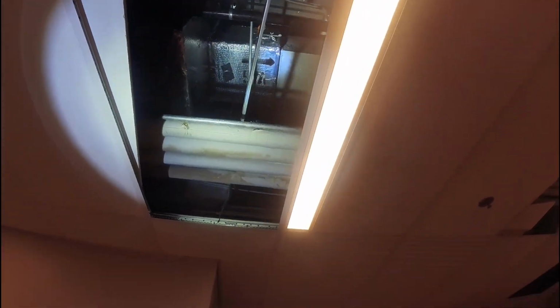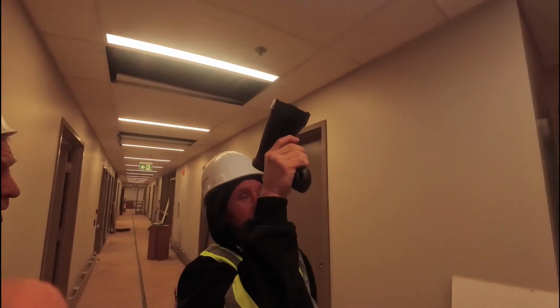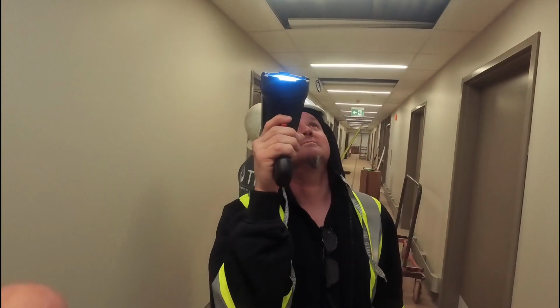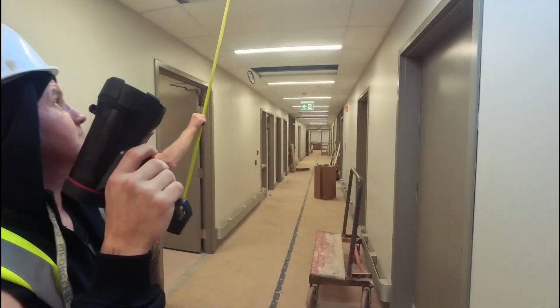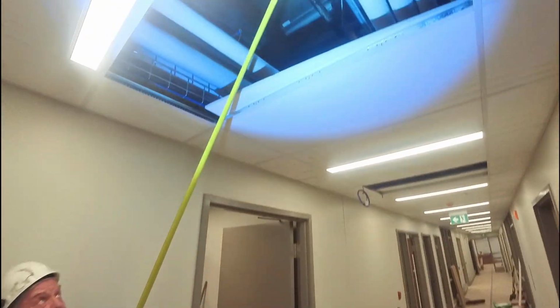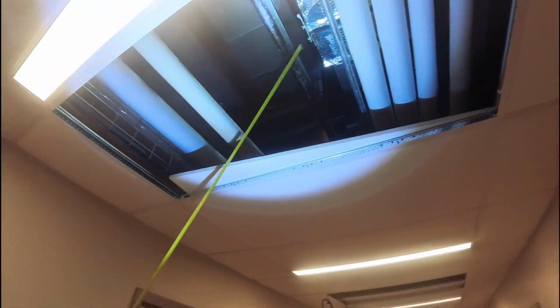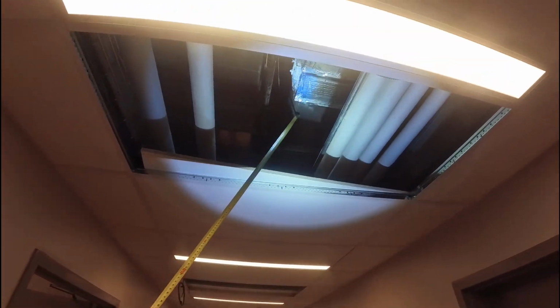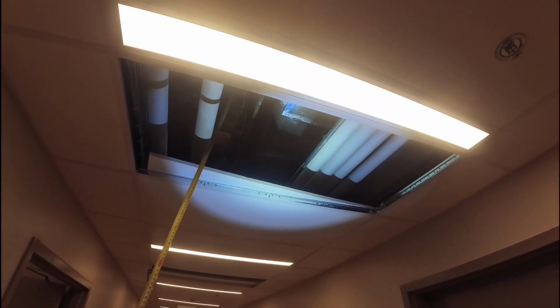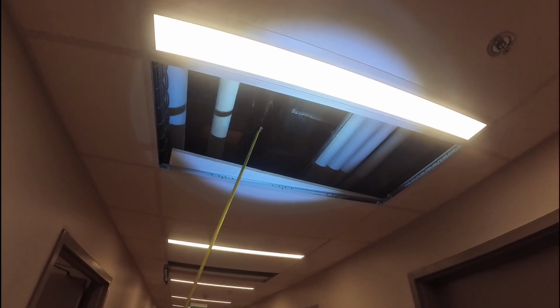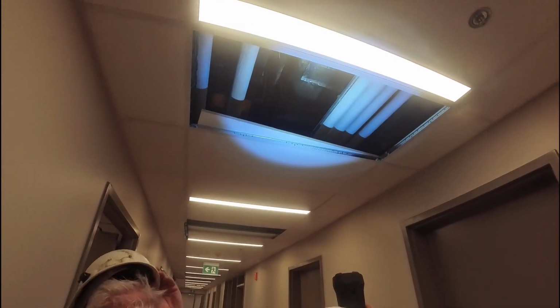So it's full of insulation already. The silencer quiets the air down. It forces the air through a fibrous insulation. Like a muffler? Like a muffler, exactly what that is. And there's the other side of your supply end of it. Again, your big balancing volume dampers tying into another silencer. So basically the same idea is on the return up above, going in both directions.